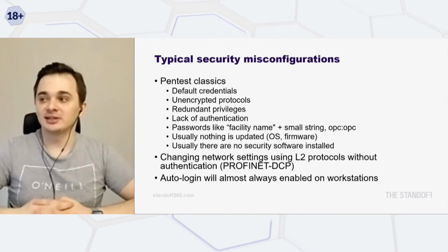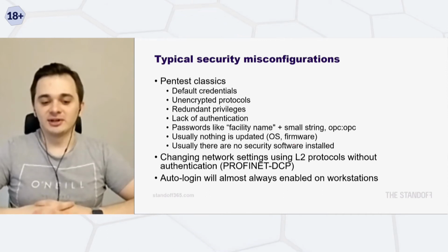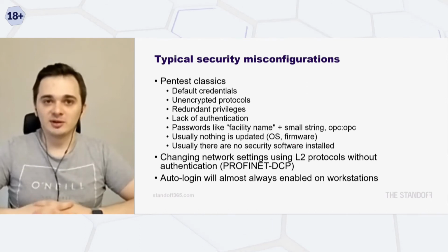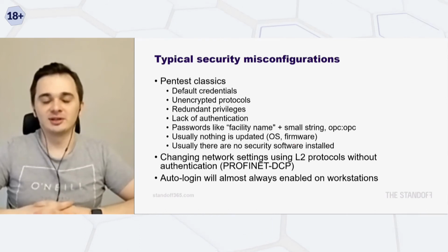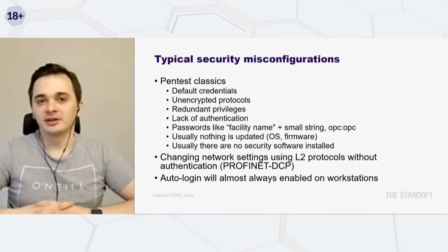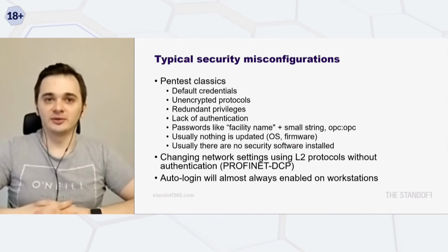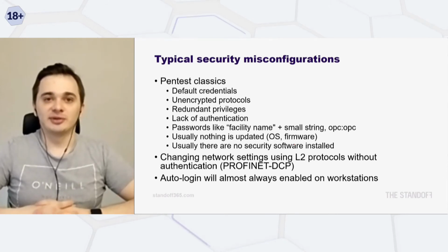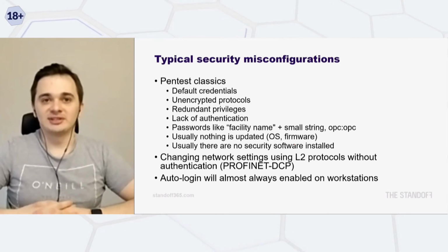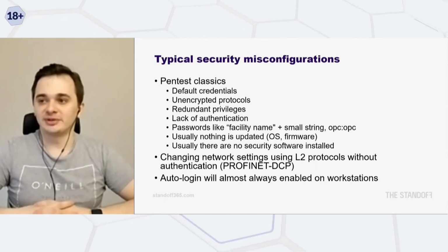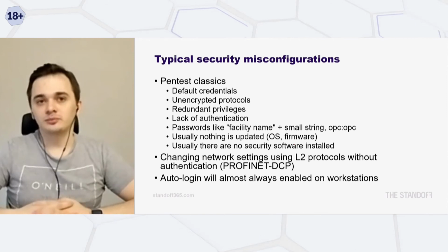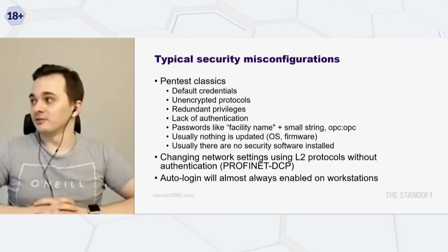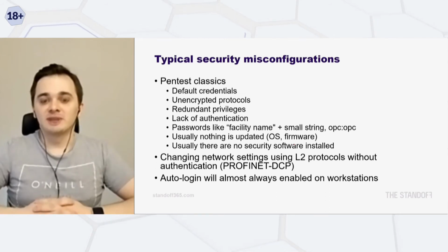Apart from default passwords, we also find simple passwords. It's a string that starts with the facility name and ends with some small string or some number. Those passwords can be found quite easily. Or you can also see passwords of the like of OPC, double colon, OPC.